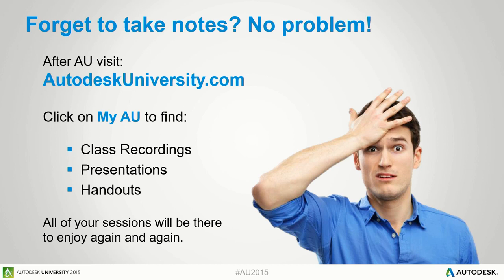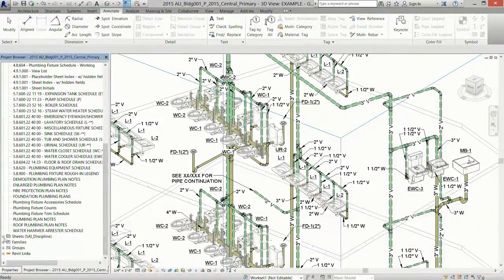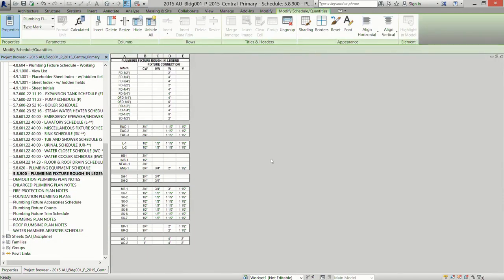Q: About quantifying what's in the model? A: You can do that directly in Revit — Revit knows everything that's there and you can schedule it. We use that for cost estimating: if I know how many three-quarter-inch elbows are in there, I can tell Revit what that costs and it'll add it all out. If you want a specific parts list for fabrication purposes, we would probably pull that into Navisworks rather than doing it in Revit.